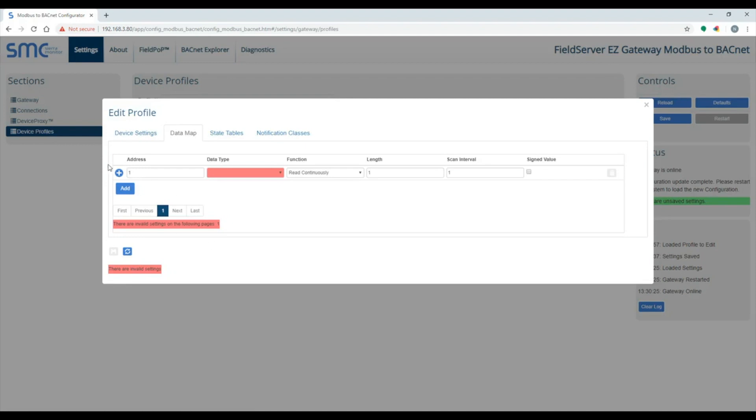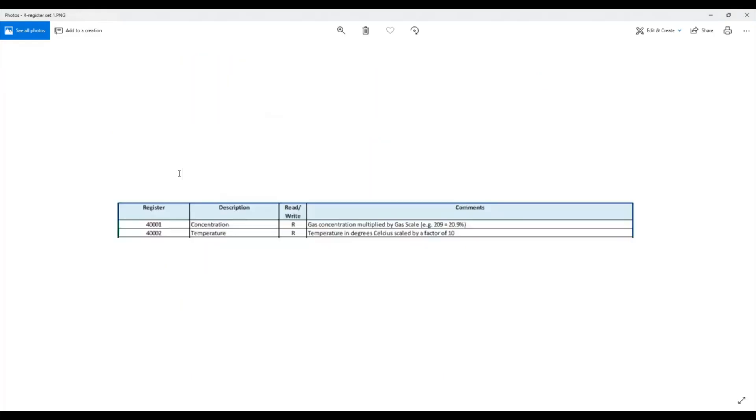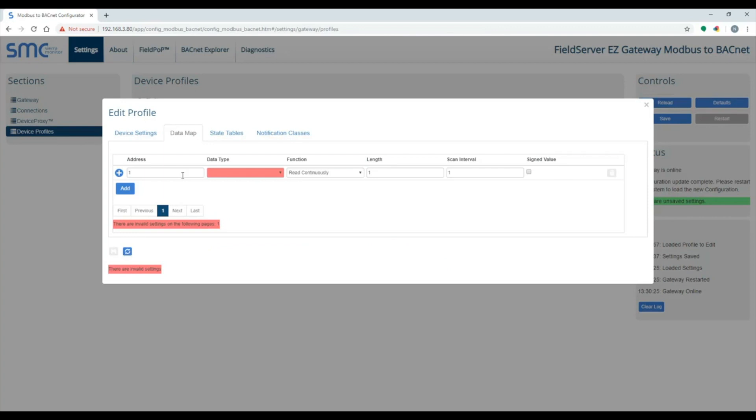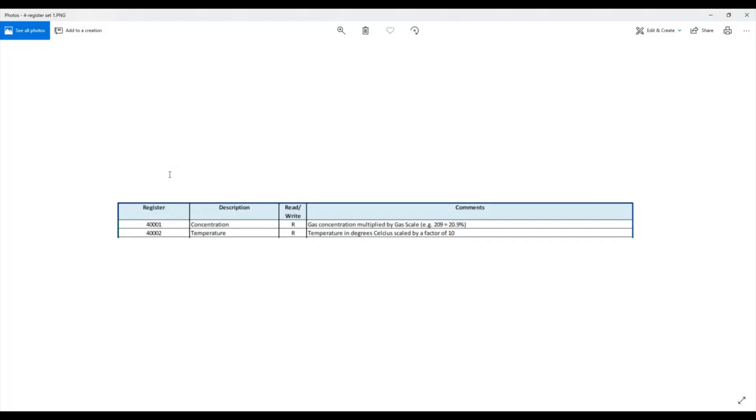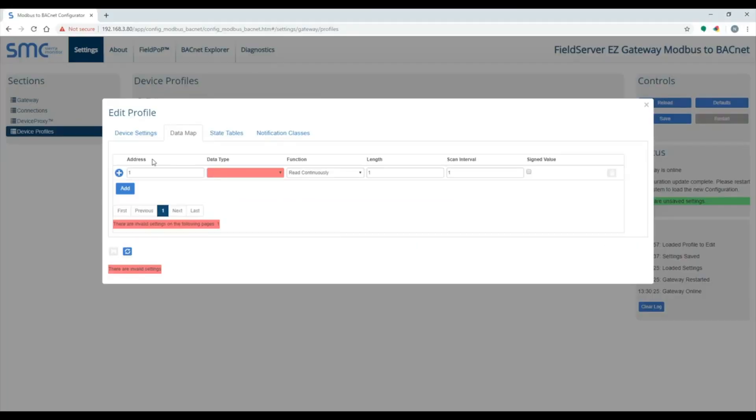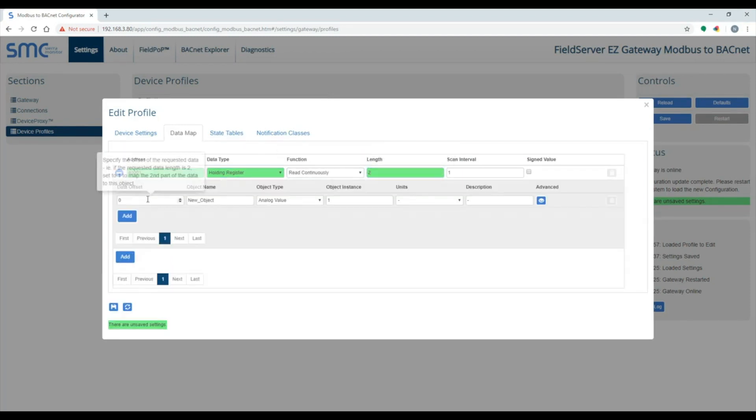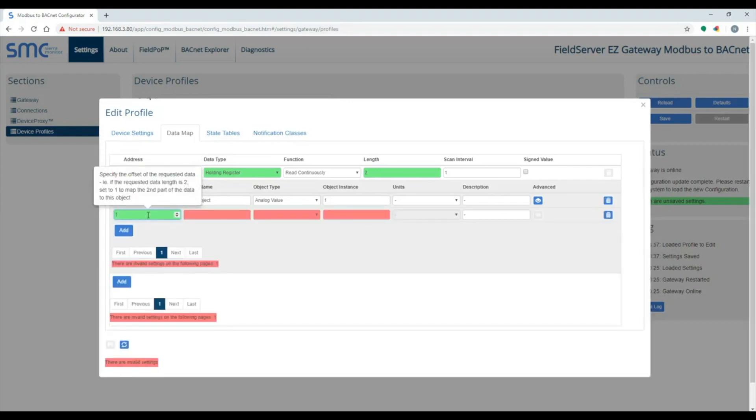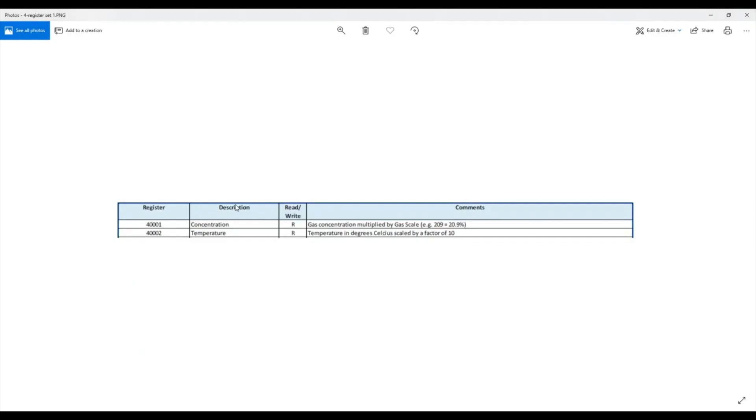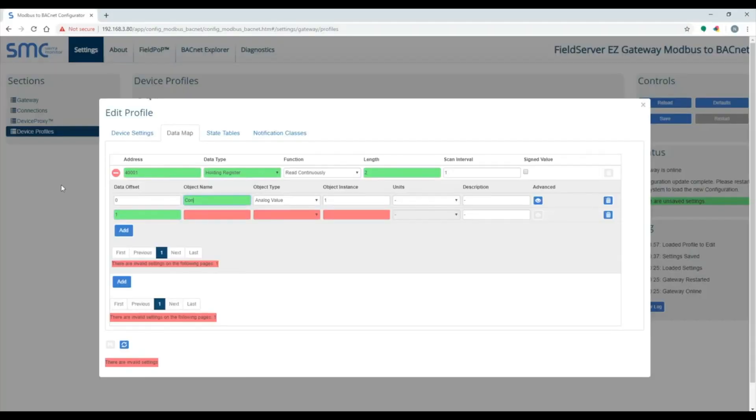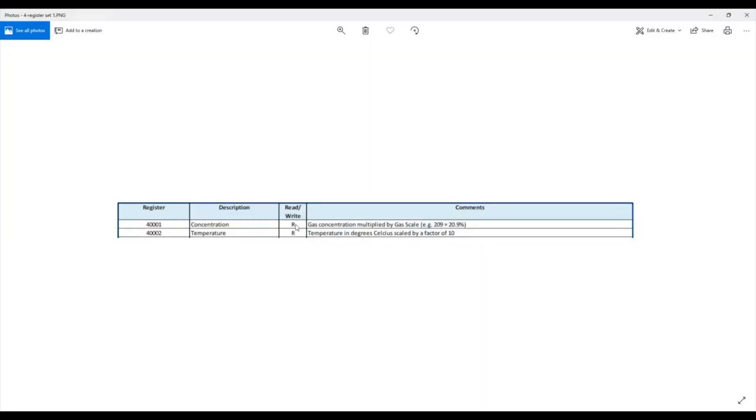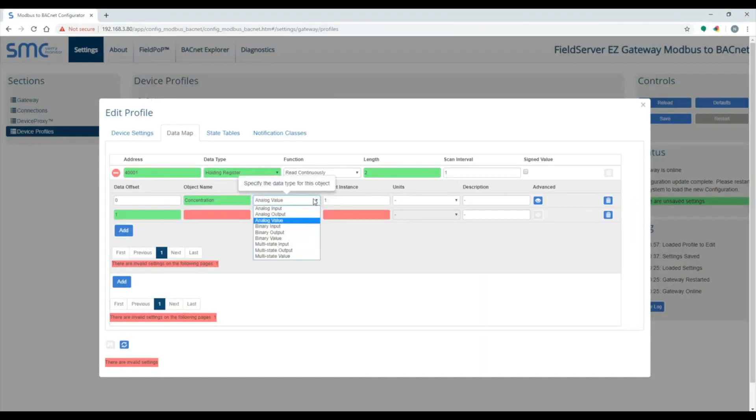The Data Map tab is where the Modbus registers are mapped to BACnet objects. The first block of registers are 48001 to 48002. The data type is holding register. The function is read continuously. Length 2 for two consecutive registers. With length 2, you have two offsets to work with, 0 and 1. Offset 0 is 48001, offset 1 is 48002.